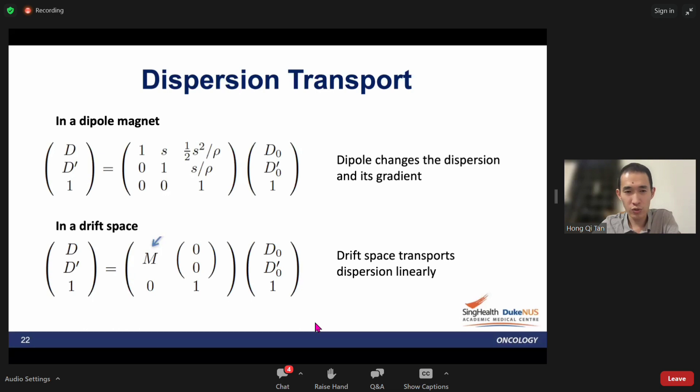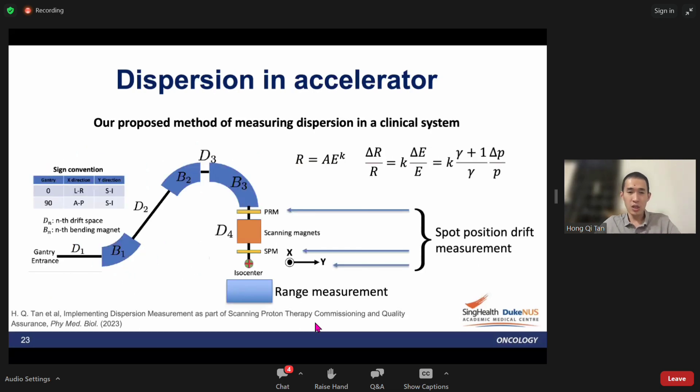Typically in an accelerator, it's actually very difficult to do a dispersion measurement. Sometimes you have to tune your magnetic field, your magnets, or your RF to actually get the deviations and measure the spot position deviations. All these things are not very easy to do in the clinical proton system, but we propose a method to measure dispersion in the clinical system.